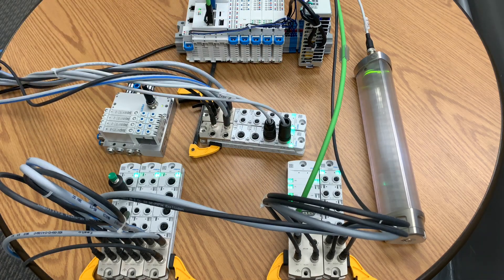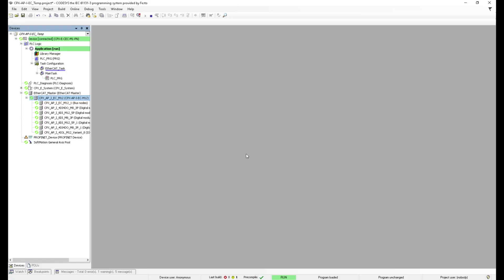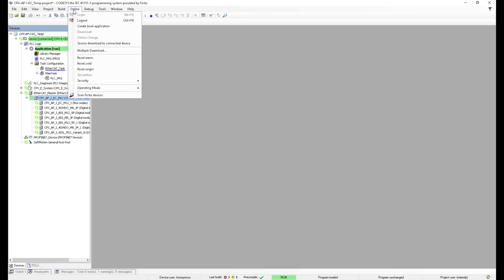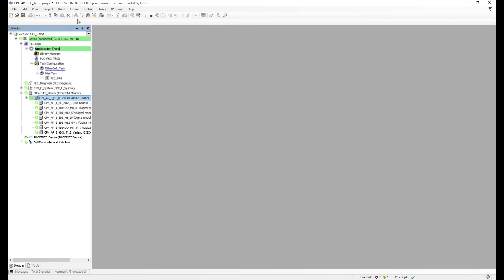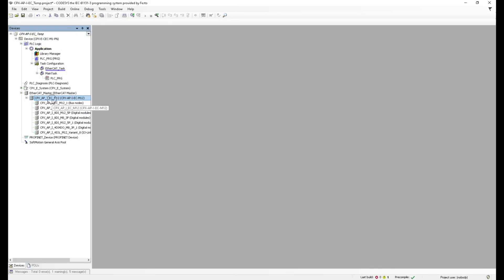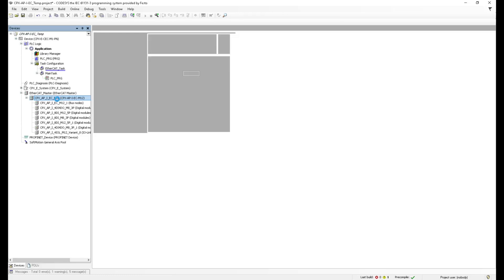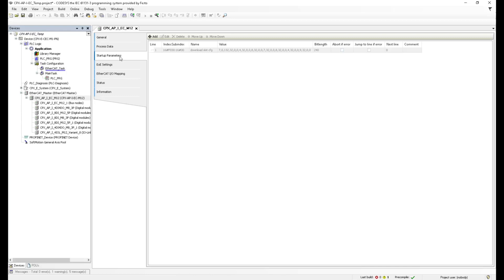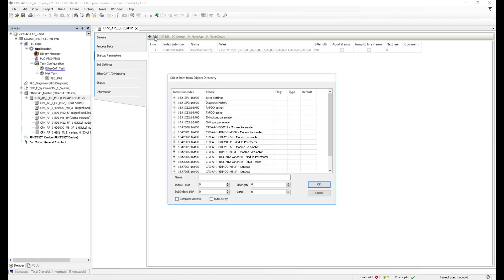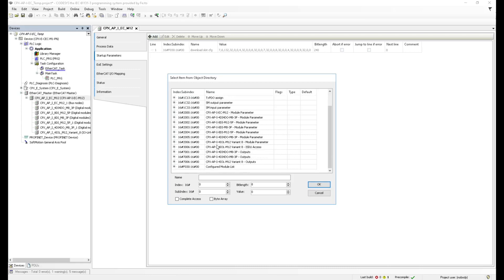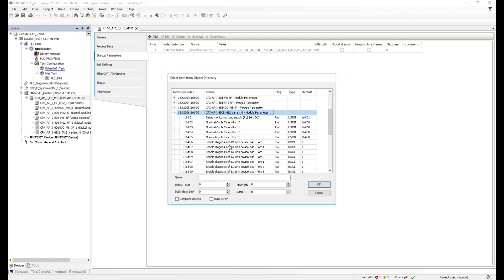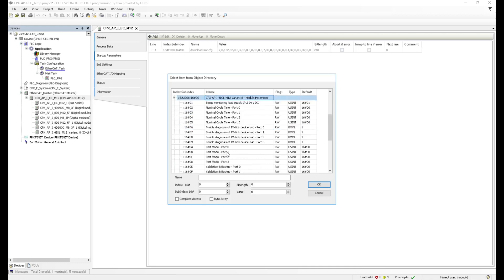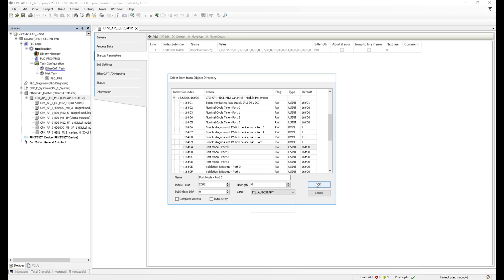How do I do that? It's pretty easy to do that in CODESYS. Let me show you. I'm going to log out and double click on the head module for EtherCAT on the slave, CPX API EC. I'm going to double click on that and then open the startup parameters. Inside of the startup parameters, I'm going to add a couple of parameters. I'm going to go to this one. This is my IO-Link module parameter. And then on port zero, where my valve manifold is at, I'm going to select this parameter. I'm going to say set to auto start.